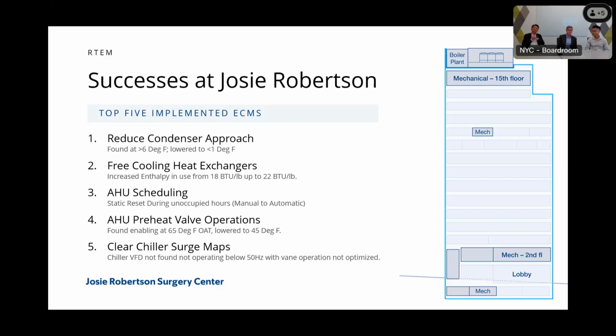Harking to the chiller surge maps, clearing the chiller surge maps is an item that comes directly from the chiller panel. So if you don't have experienced people, or the people on site are busy doing other things, answering hot and cold calls, running around, handling other items, that's an oversight that might occur. So thanks to RTEM and utiliVisor watching over, we observed that the chiller had never gone below that 50 hertz limit, and we were able to call out that item for the surge maps to be cleared.